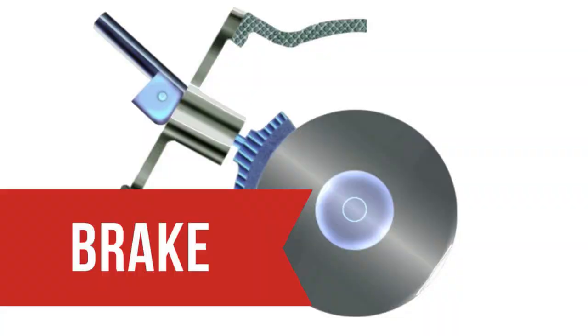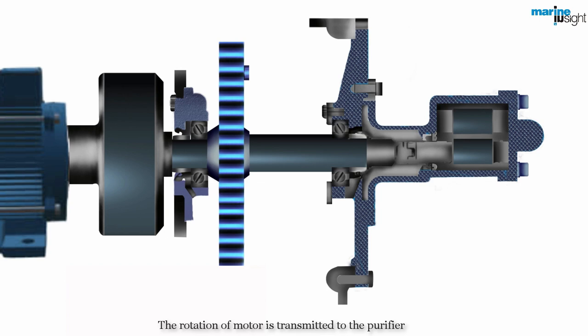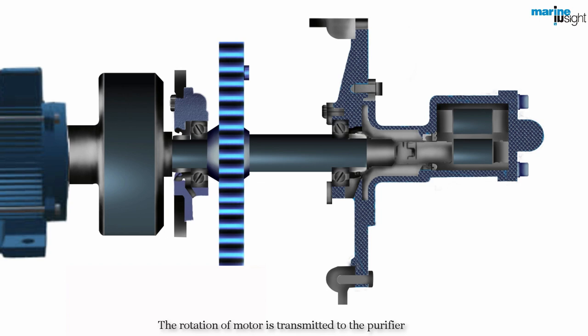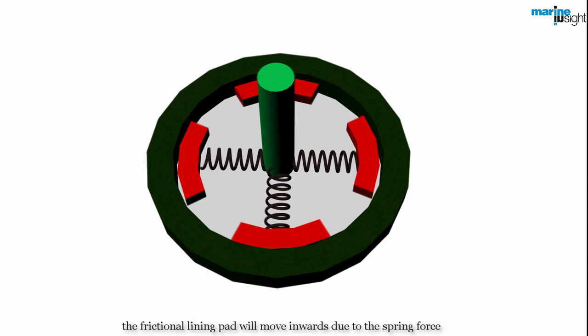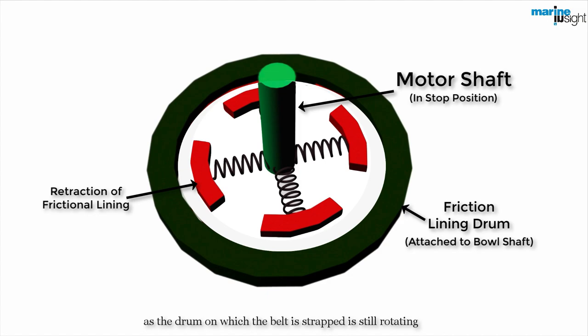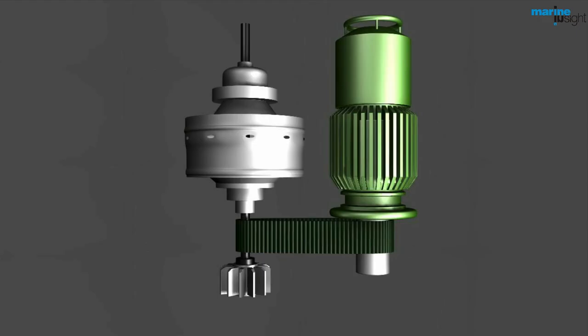The rotation of the motor is transmitted to the purifier using frictional clutches. During stopping, as the motor comes to the stop position, the frictional lining pad will move inwards because of the spring force. However, the shaft carrying the bowl will continue to rotate as the drum on which the belt is strapped is still rotating.